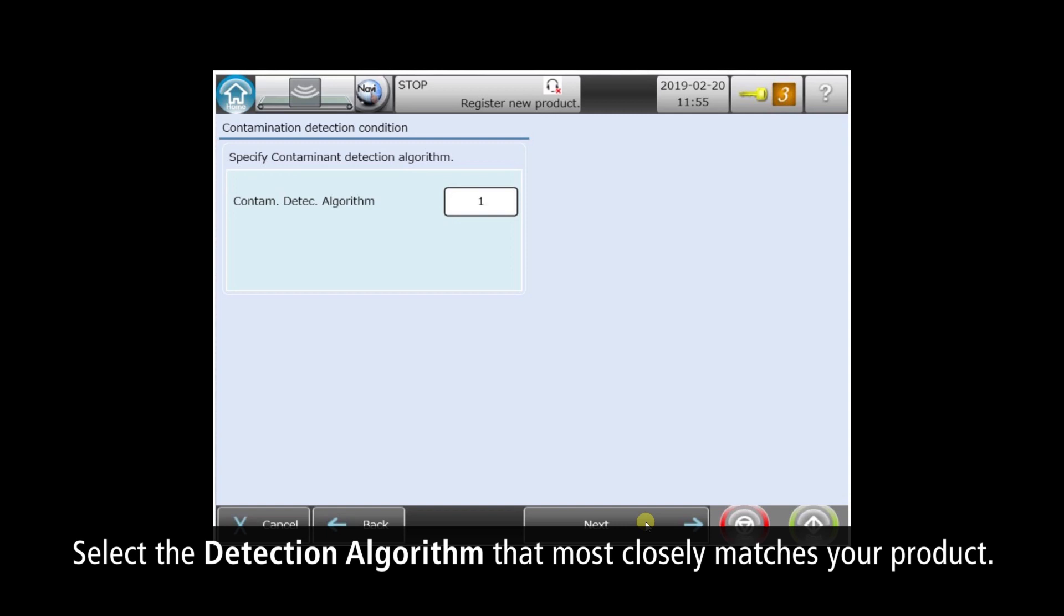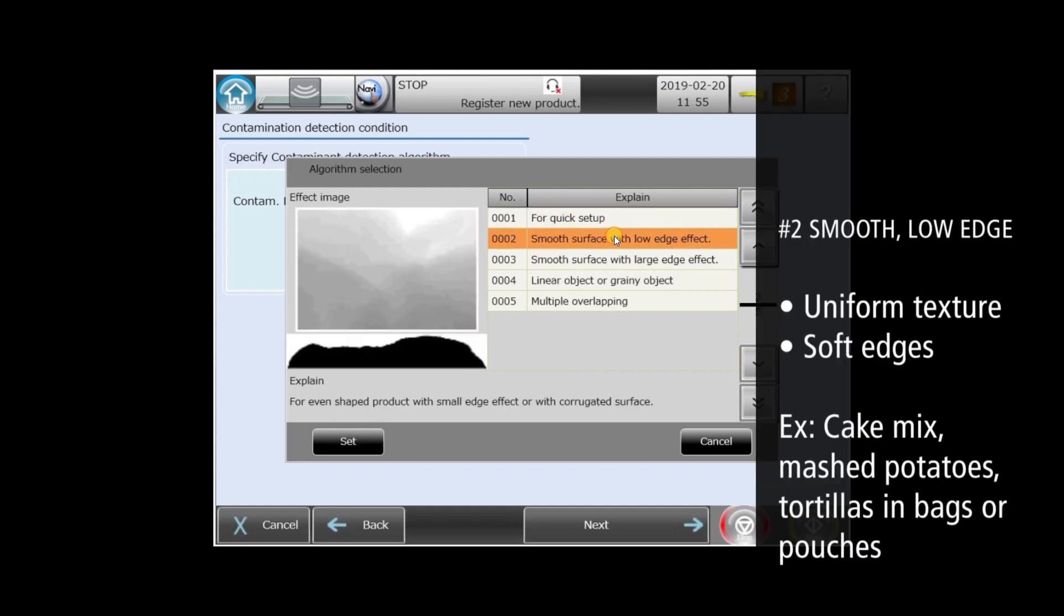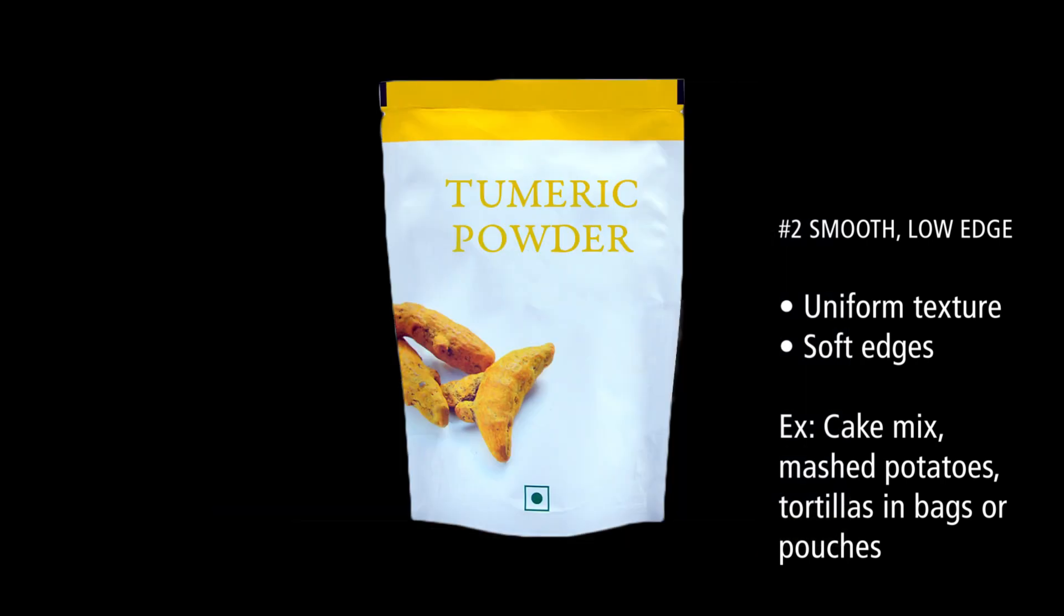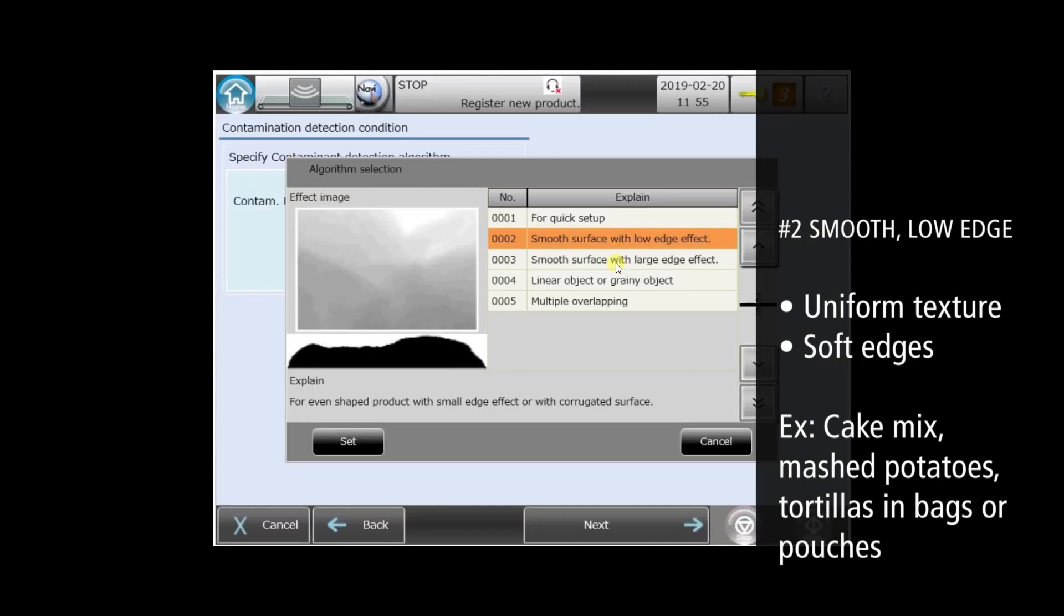The XR75 comes with special detection algorithms that cover the majority of applications. We'll skip number one, which is a legacy algorithm. Number two is for smooth products with soft edges, like powders and pouches. Notice how the example X-Ray images reflect this product type.